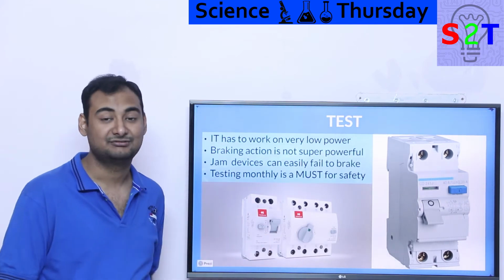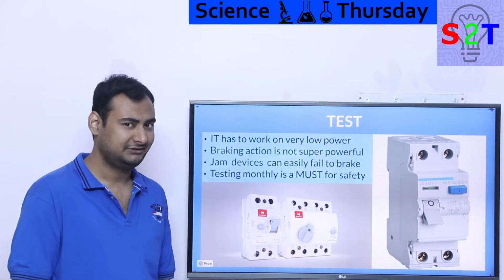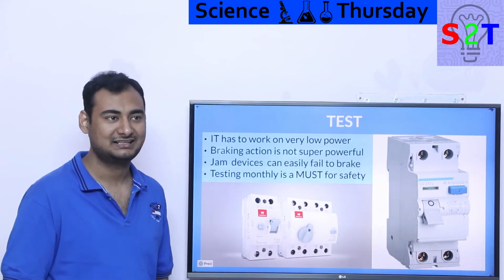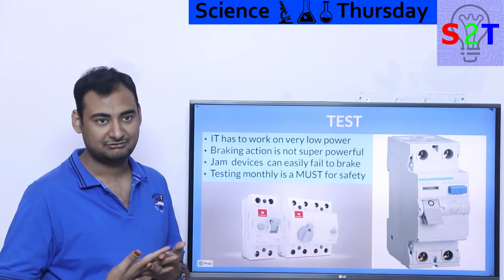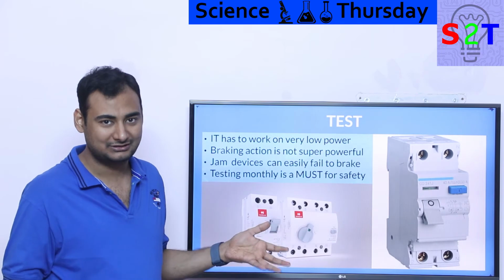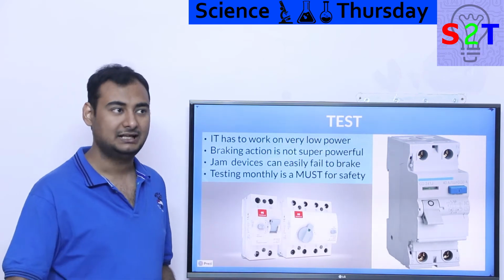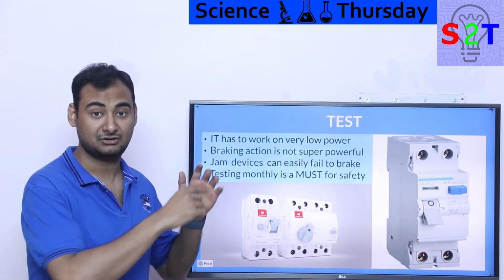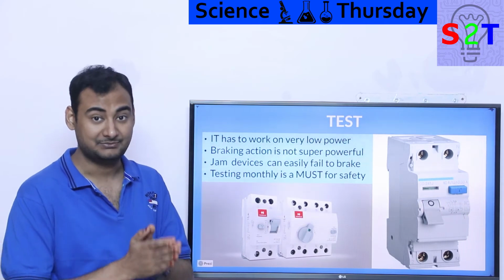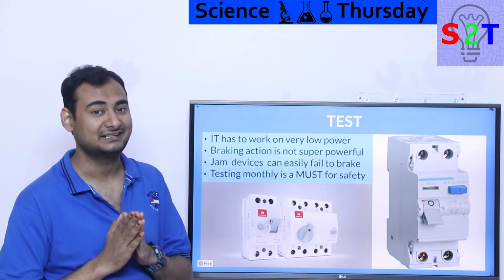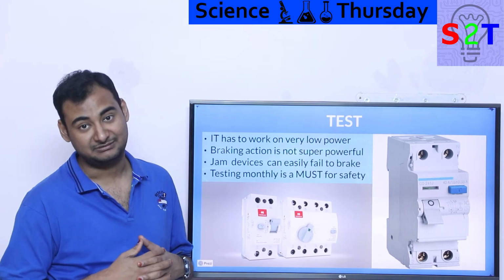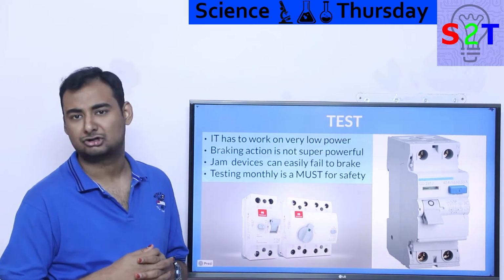Well, reality is it's working on very low power. That third coil, that's not very powerful, and inherently it's designed to trip on a very low amount of current, because it's not supposed to give you 1 ampere of shock, and then it's like, oh, whoa, whoa, whoa, I think somebody is getting shocked, let me trip it. No, it has to work on milliamperes. For Indian examples, it has to work inside 30 milliamp. Now if you multiply 30 milliamp by 220 volt, that's not a lot of oomph.